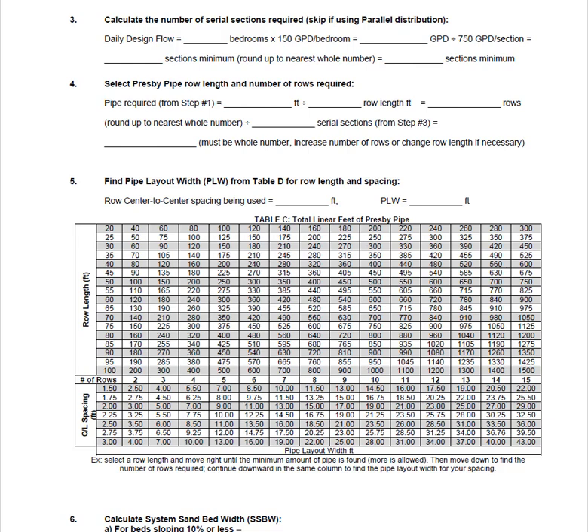Because we are using serial distribution, we're going to continue with step three. Our daily design flow is calculated using the number of bedrooms — six — and at 150 gallons per day per bedroom, that brings us to a total flow of 900 gallons per day. Since 750 gallons per day is the maximum flow allowed in a serial section, we divide 900 by 750, which gives us 1.2. After rounding up to the nearest whole number, we can see that we will need at least two sections in this design.